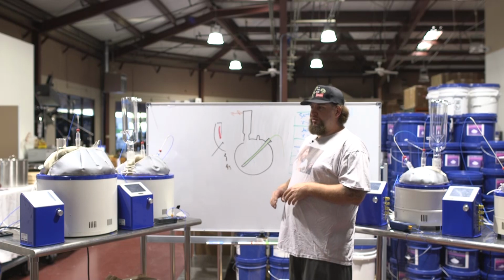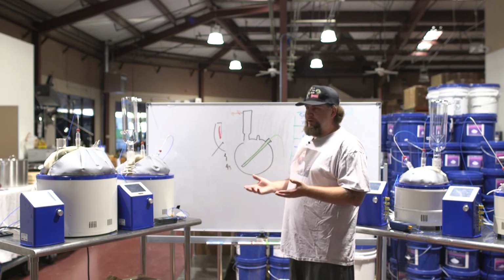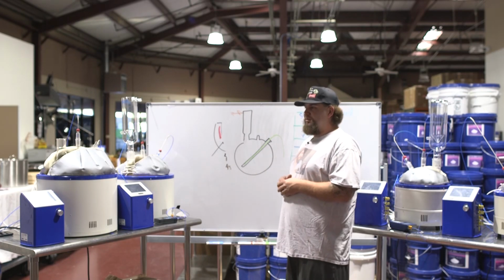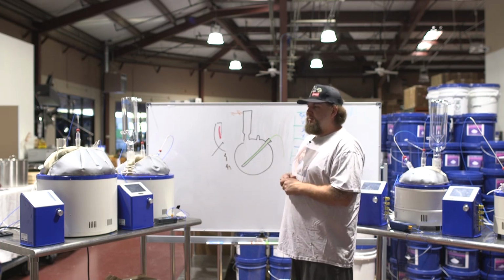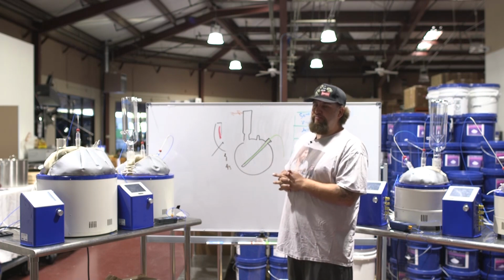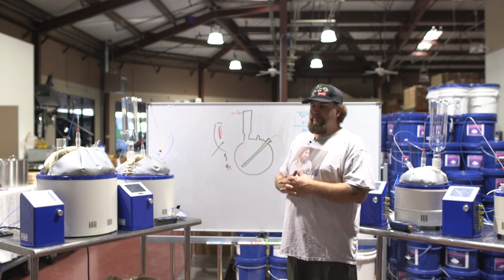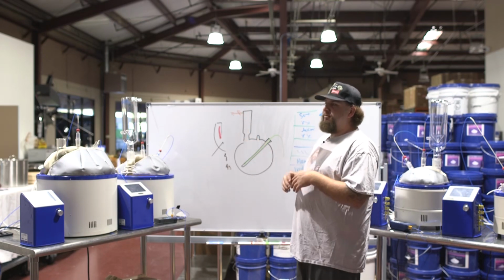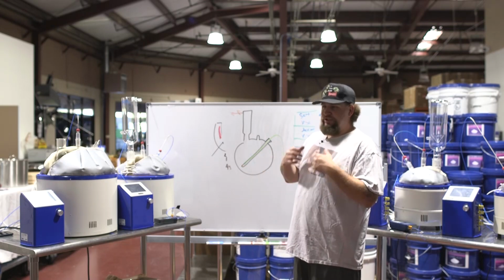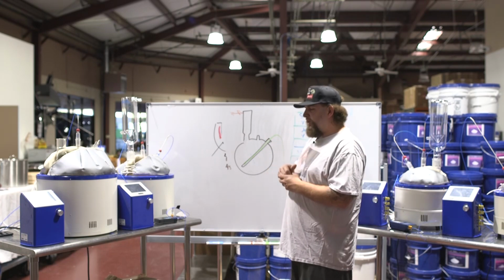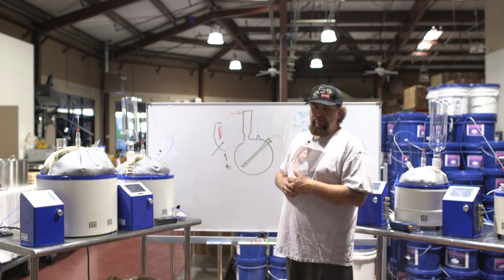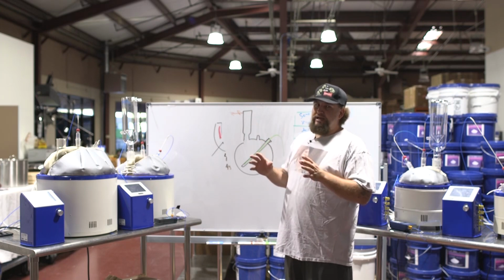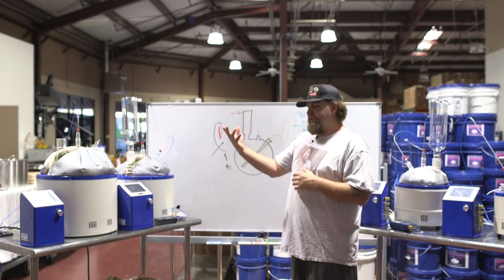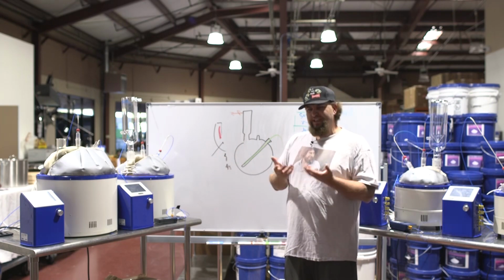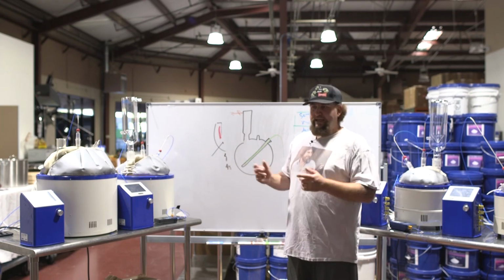We then will do an auto tune. This is primarily used just to be sure you have the most amount of power gauged to your zone. If you auto tune to a higher temperature, you will have more power at that higher temperature. If you auto tune slightly lower, you'll have a medium amount of power. It's still a lot of power, but it's not just dumping voltage out. What I normally do is auto tune to 150 Celsius. By doing that, if you're at 175 or 200, if you set it to a high temperature, it's not just going up there and dumping out so much energy that the system overheats. It's dumping as much energy as it would need to get to about 150. But it's really accurate that way.